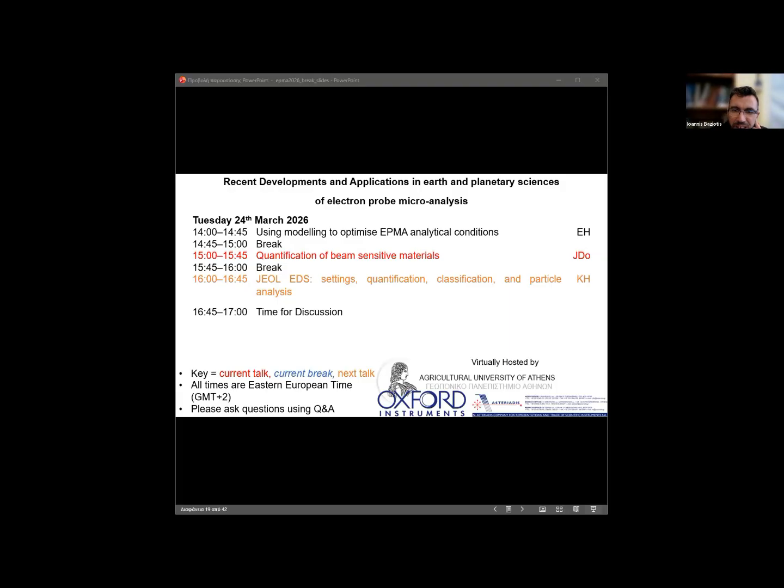One more question. Can TDI correction be applied when doing analysis combining EDS with WDS? In principle, it could be. I haven't done it yet, but we can acquire EDS elements with our WDS elements. Right now we don't acquire TDI on EDS because you'd have to acquire a full spectrum for every time interval, so it would be a bit of work. I've been asked about this before, and I've hesitated to get involved in it.